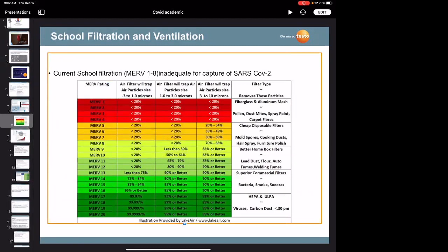But this is the reason why ASHRAE states that let's go back and baseline test the system, because every mechanical system has a min and max pressure drop capability on the suction side to accommodate filter and filter loading. So I would not assume that today's MERV 13 filters are going to be a big problem, especially from a performance standpoint or reliability standpoint for the mechanical system, because their engineering is getting better. The pressure drops are lower, and you just might have more frequent changes of a MERV 13 than what you did before COVID. And remember, these values or the need to use MERV 13 are guidelines only for when a pandemic state exists. So when a pandemic is deemed to be over, you don't need to use MERV 13 filters. So it is a temporary situation.